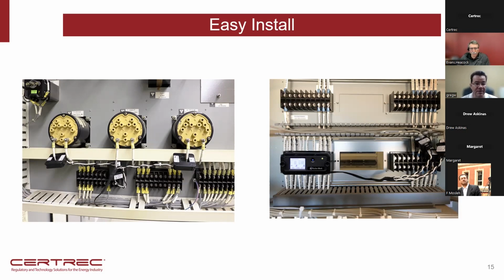We just snap them together, lays in the tray. And so in about 10 minutes, then we're monitoring 3-phase volts and current. We come through the other mounting bolt with an Ethernet cable, actually a little miniature insulated cable goes through the other mounting bolt, and we terminate that with an RJ45 connector. We've even done some fiber optic installations. And so we communicate through to the server, power the device, PoE, over Ethernet cable right through the mounting bolt. We can also power off phase voltage as well, and then provide the visibility very quickly and without an outage, without any new wiring.